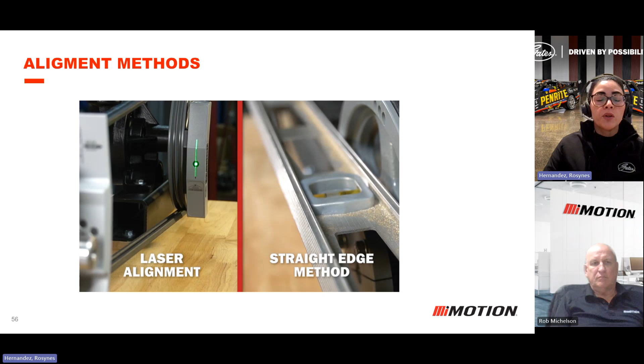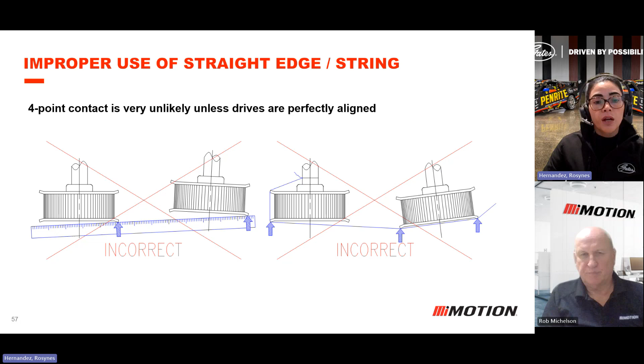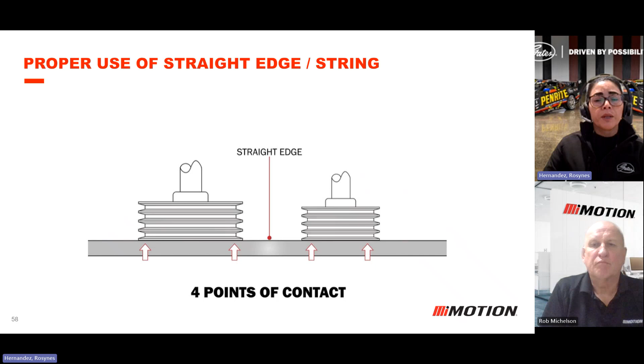So what are you looking for here? You just need 4 contacts between your driven and driving pulley. In these cases, we emphasize that two of these images are incorrect because the pulleys are not aligned, so you'll have a lot of problems with that. This is the correct way to check using a straight edge to get 4 points of contact. However, this is not as accurate as using the alignment laser tool.